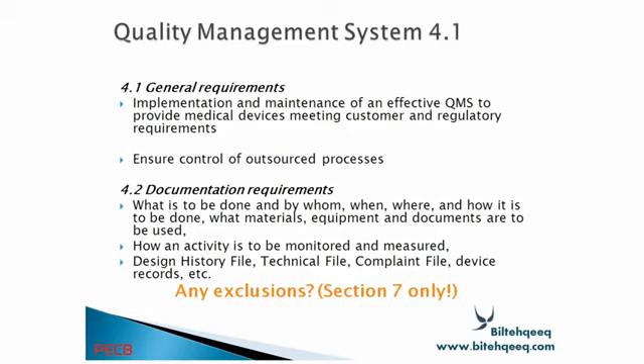Section 4.2 covers documentation requirements: what is to be done, by whom, when, where, and how it is to be done; what materials, equipment and documents are to be used; how an activity is to be monitored and measured; design history file, technical file, complaint file, device record, and any exclusion. If there is any exclusion, we have to describe it. We have to develop proper documentation procedures defining who is responsible for what and who is doing what.